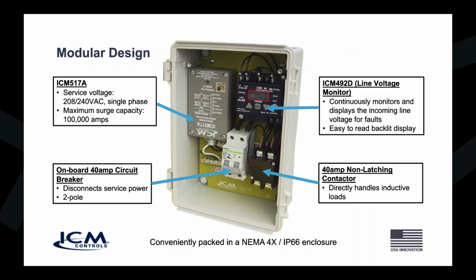So here's the parts inside. Again, service voltage for this model is 208, 240, which is pretty much most of what you're going to see. Maximum surge capacity of 100,000 amps. All right. Your voltage monitor, again, pre-wired, set up for 240 volts, continuously monitoring and displaying the incoming line voltage for faults. Easy to read backlit display, so you can read those conditions and those faults in low light conditions. Also an onboard 40 amp circuit breaker, which disconnects you. It's basically a disconnect switch that disconnects you from the power. And there's a non-latching 40 amp contactor that directly handles the inductive loads, much better than those block relays, which could be latching.